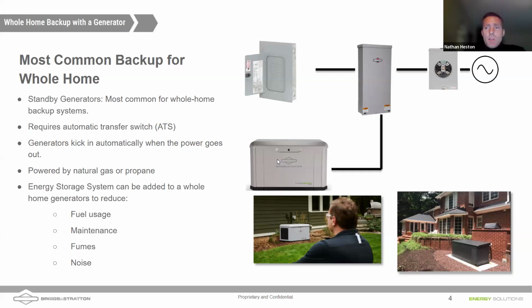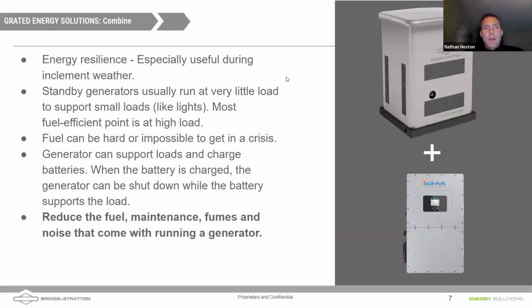So the residential systems that you can see function in a fairly simple way. There's a transfer switch, and either the home loads are being run off of the grid, where the grid passes through a meter and through a transfer switch and covers the home loads. In the event of a grid down time, the generator will auto start based on auto mains sensing. It senses the grid goes down, it starts up, that energizes a transfer switch, it pulls a solenoid into the position of the transfer switch, and then the generator can feed the home. So it's either or. It's either the grid or it's the generator powering the house. So that's the typical way.